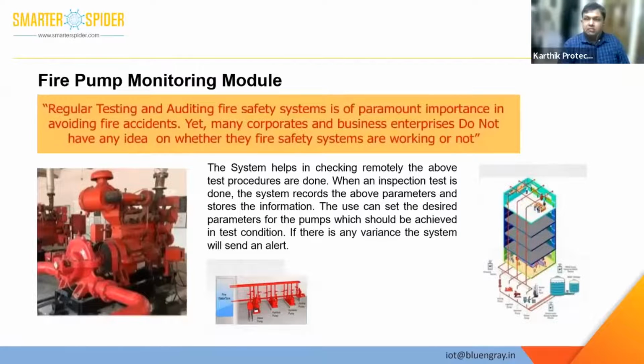When you're doing a regular fire drill, as per the norm, depending on how large the facility is, sometimes they are required to do 30 minutes or 1 hour. We have seen cases where the supervisor runs the system for only 5 minutes, but in the report they write it as drill done as per norms, that is, for the required time. In due course, we have seen that he or she knows how much diesel gets consumed during the drill, so they remove that diesel and sell it for personal gain to the trucks or autos that come for delivery. So it's a very critical aspect which we found.